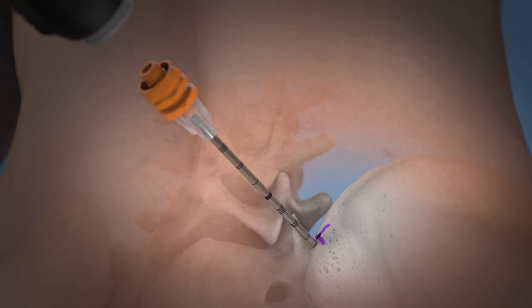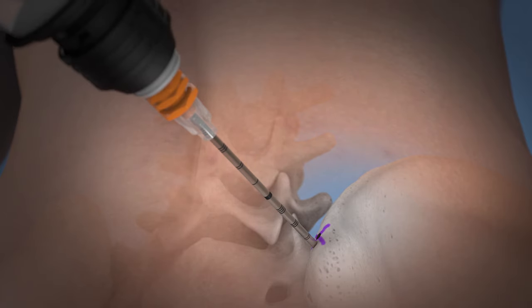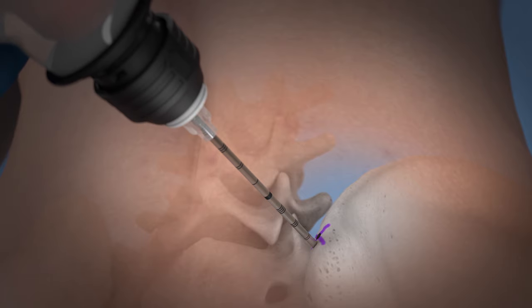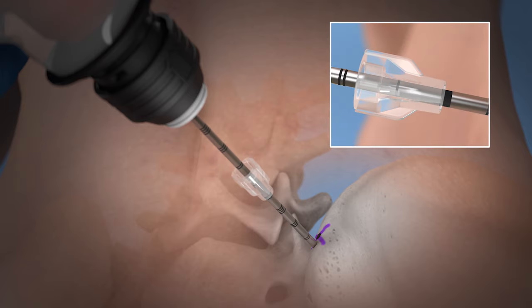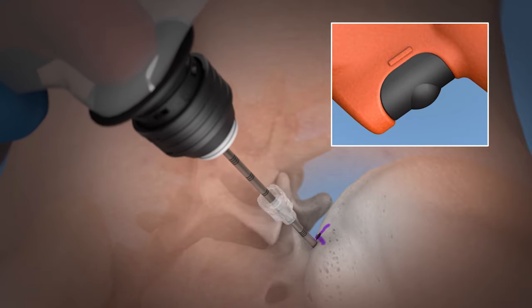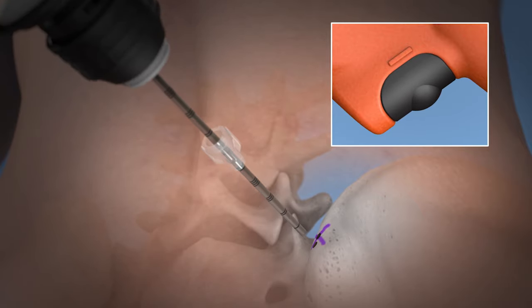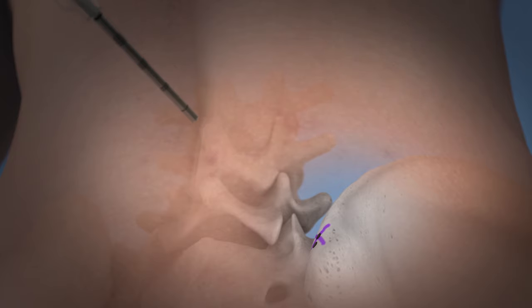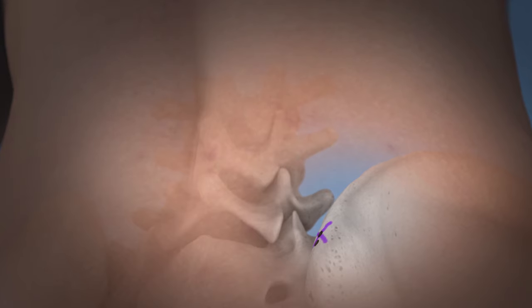Reattach the driver to the needle by gently pushing down until the connection click is heard. Move the depth guide down from the hub of the needle to desired core length above skin surface. Engage the trigger continuously while pressing downward then upward in one smooth motion while observing centimeter marks on the needle, advancing no deeper than the depth guide.